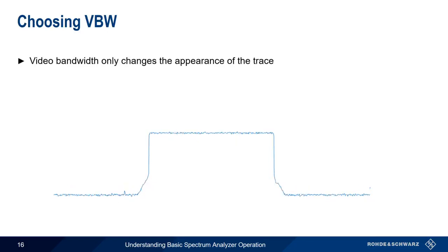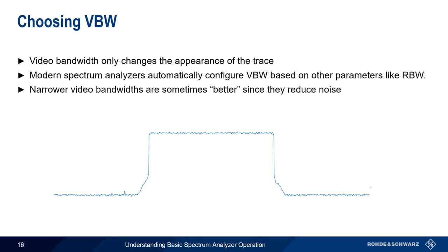So how do we choose our video bandwidth? Video bandwidth only changes what the trace looks like, so to a certain extent the correct video bandwidth setting depends on the application. That said, most modern spectrum analyzers will automatically configure and update video bandwidth based on other parameters like resolution bandwidth. In many cases, a smaller or narrower video bandwidth might seem desirable since it reduces noise on the trace. But just like resolution bandwidth, video bandwidth does have an effect on the sweep time. The smaller or narrower the video bandwidth, the longer the sweep time.